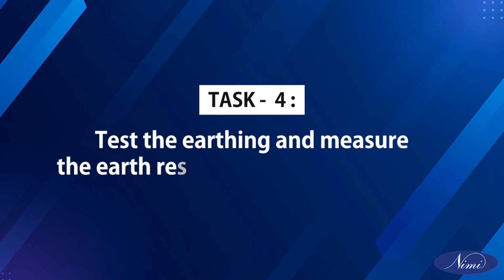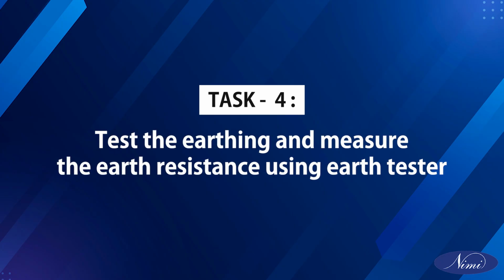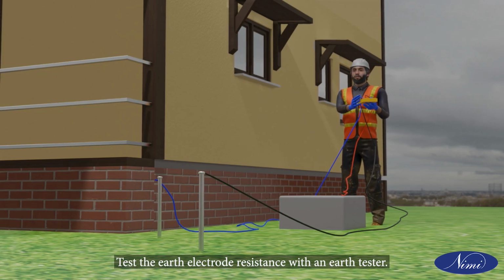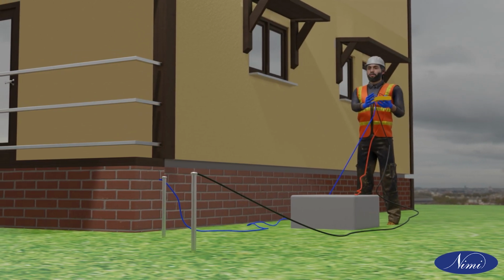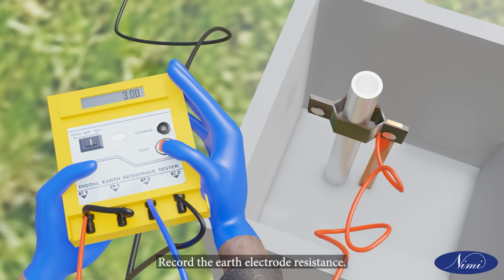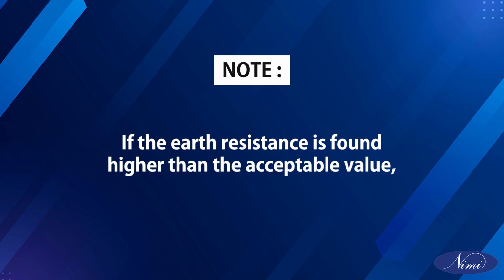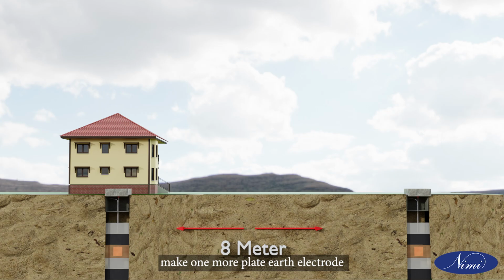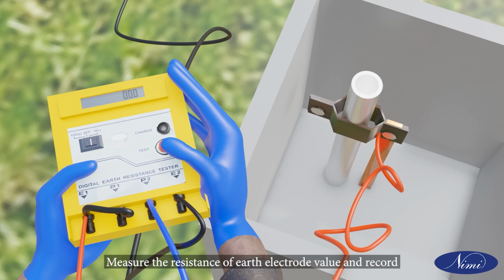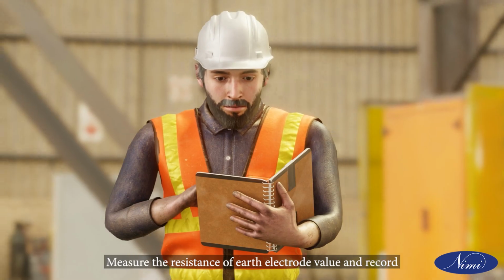Task 4. Test the earthing and measure the earth resistance using earth tester. Test the earth electrode resistance with an earth tester. Record the earth electrode resistance. Note: if the earth resistance is found higher than the acceptable value, make one more plate earth electrode at a distance of 8 meters from the earth electrode and connect both of them in parallel. Measure the resistance of the earth electrode value and record.